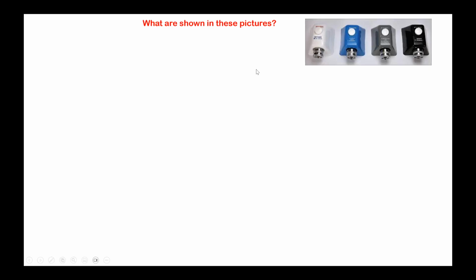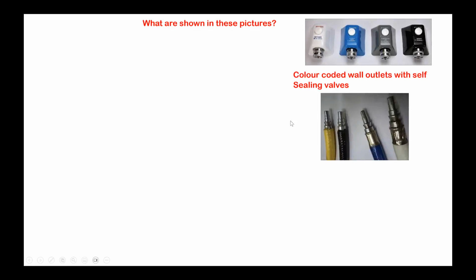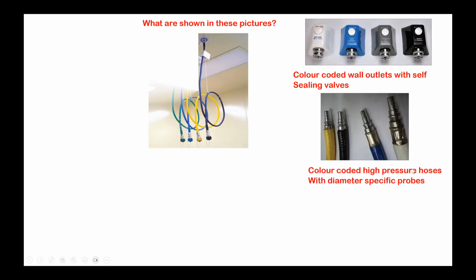Why are you taking so much time? Non-interchangeable screw thread, color coded wall outlets, self-sealing valves. Okay, that is the wall outlet with probes. Those are the color coded hoses with the probe. So this is called the probe portion. These are all the high pressure hoses to deliver the gases. Color coded high pressure hoses with their diameter specific probes.